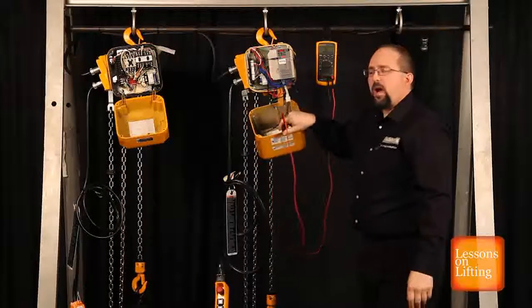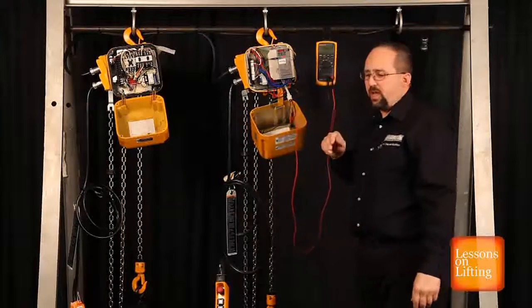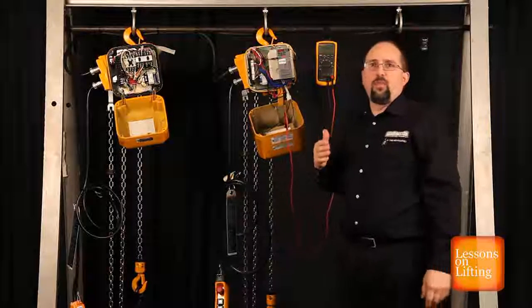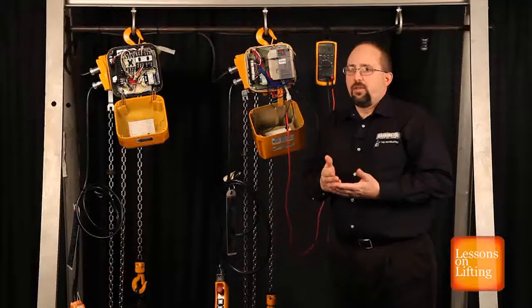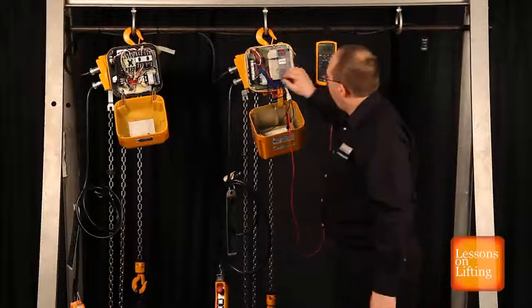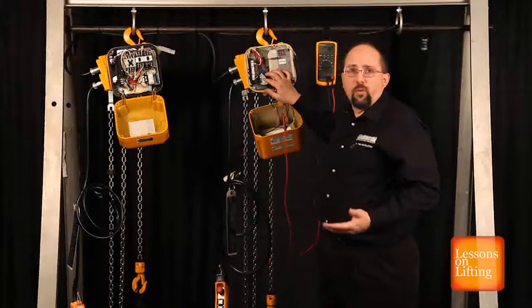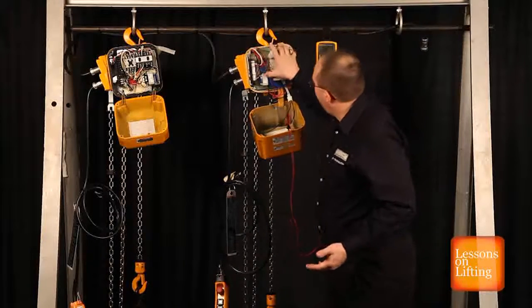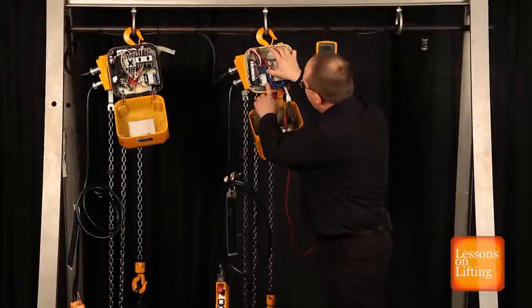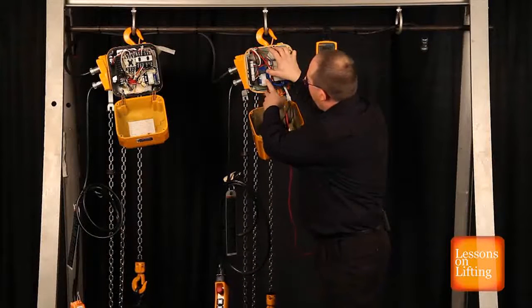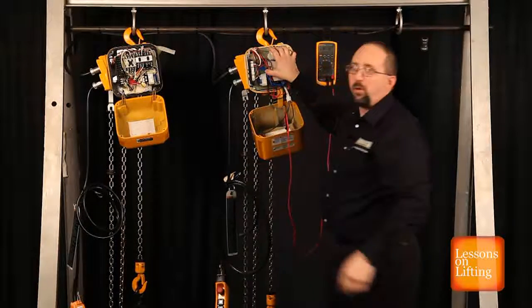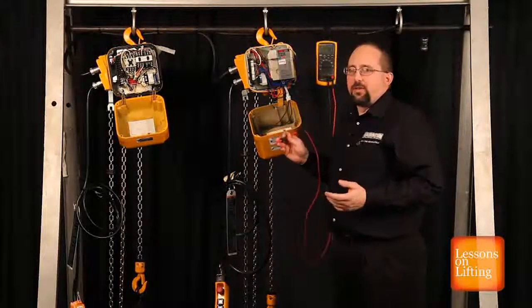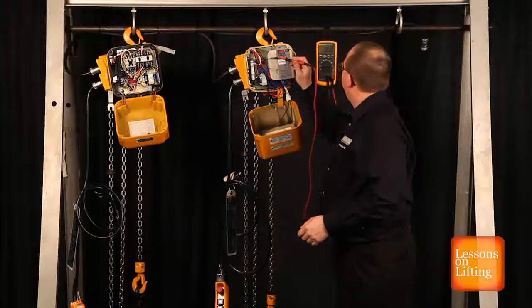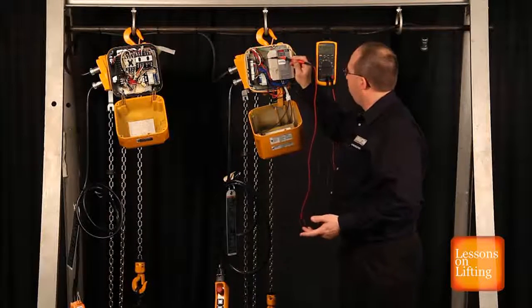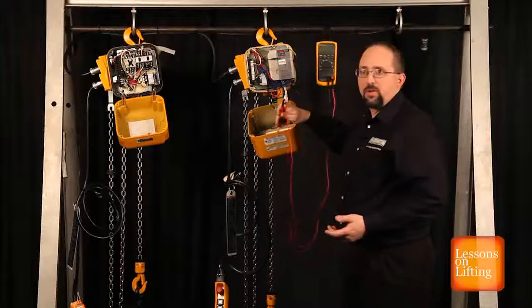You might be asking, well, how do I know what control voltage should be? Control voltage on all of our products, standard, is 110 volts. But you can get 48 or 24 volt control. So listed on each of our transformers, it's going to tell us what the output voltage is, 105 to 119.4 volts. So we know we have 110 volt control. All right, we do have 110 volts, so we know that the transformer is good.